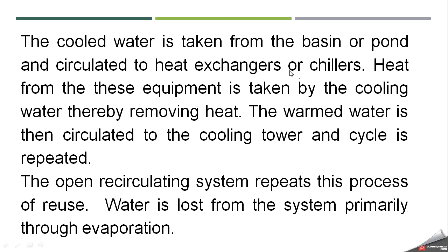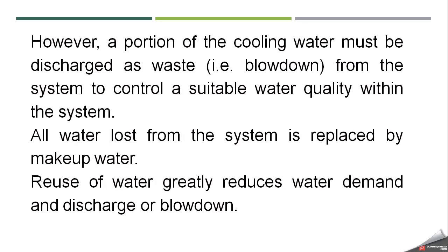The cooled water is taken from a basin or pond and circulated to a heat exchanger or chiller. Heat from the equipment is absorbed by the cooling water, removing the heat. The warm water is then circulated back to the cooling tower and the cycle is repeated. The open recirculating system continuously reuses water, with water lost primarily through evaporation. However, a portion of the cooling water must also be discharged as waste, known as blow down.